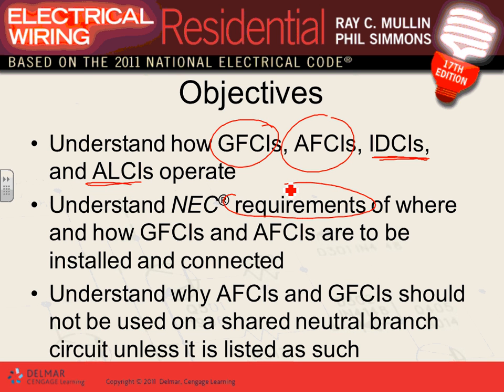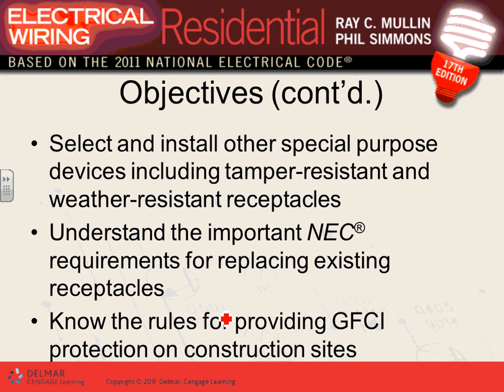Where do you need to put AFCI and GFCI in a house? And when you share a neutral in a multi-wire branch circuit, it will not allow the AFCI or GFCI to do its job. So you cannot share a neutral unless the AFCI or GFCI is listed and rated for a shared neutral. That's basically what we'll be talking about, guys.